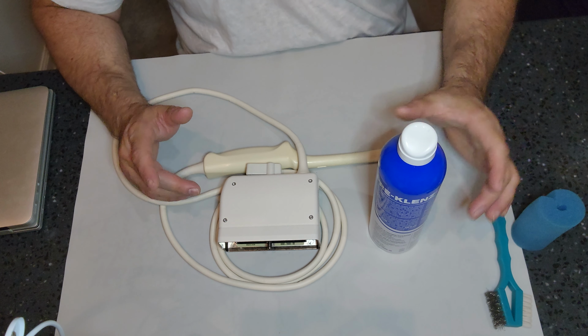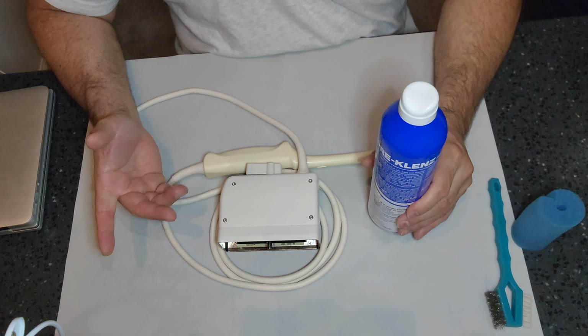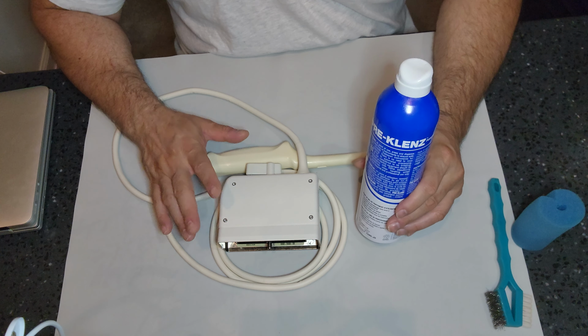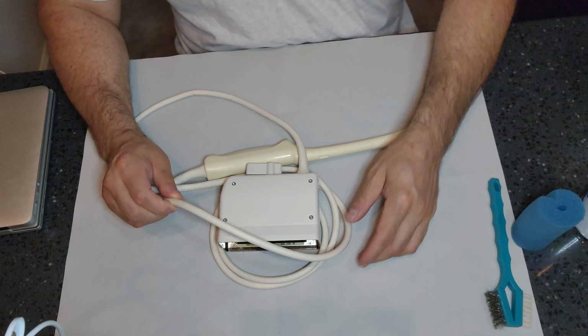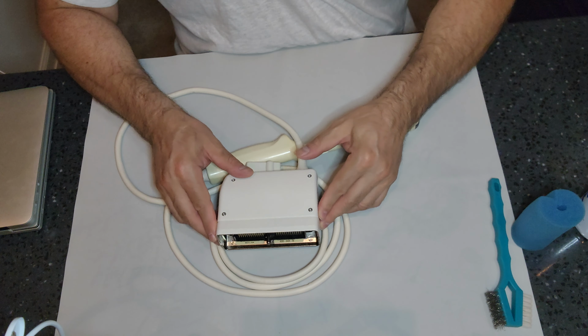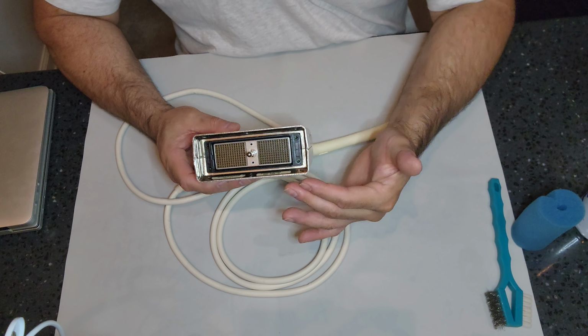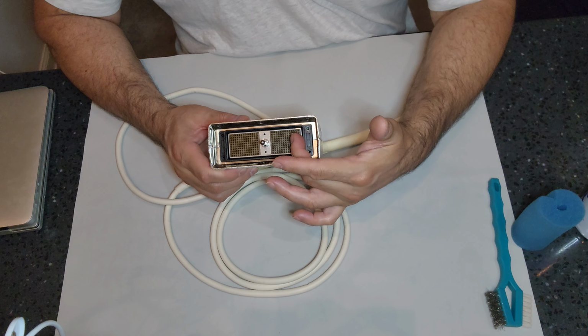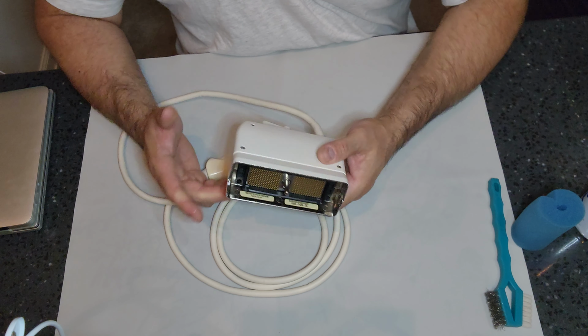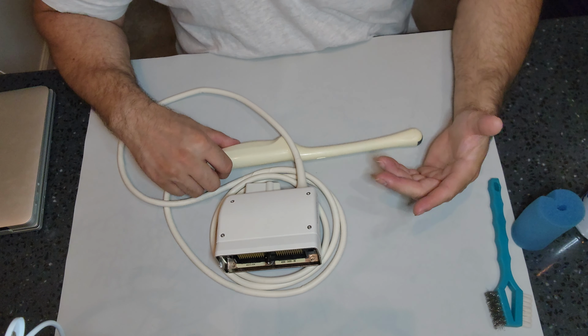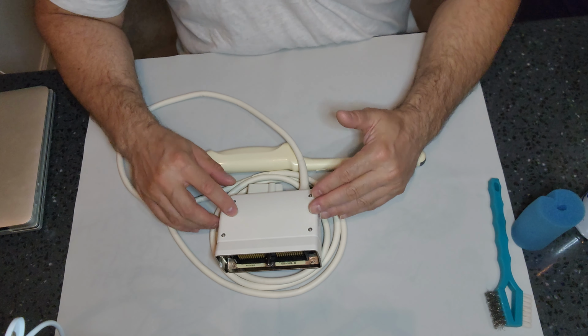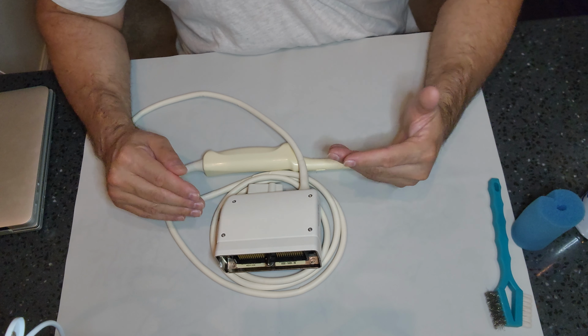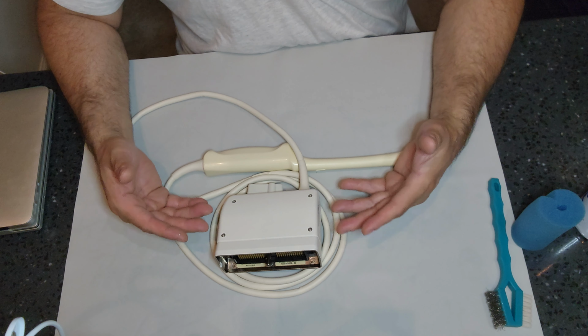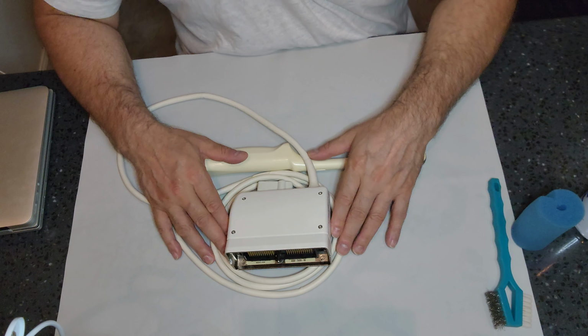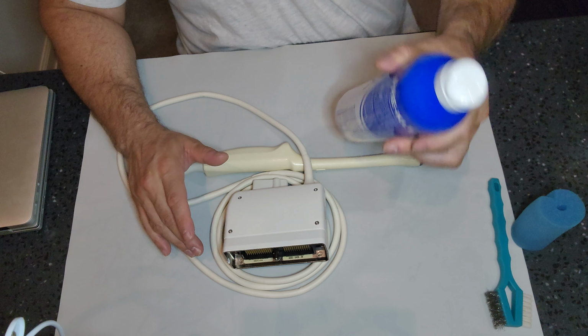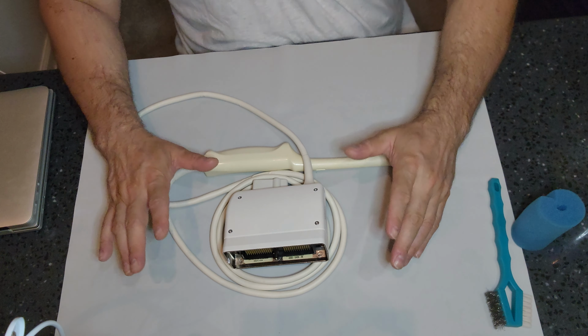Again, we have to look at these IFUs. Can we use an enzymatic spray? Because I've seen places use enzymatic sprays on probes and they wind up damaging the probes. They'll spray the cords and the cords wind up getting tinted from the enzymatic, or they spray the connector box and cause corrosion in there. Because we can't get that enzymatic spray off there, so we wind up having to use some water, and then we cause further damage. So in my opinion, honestly, these probes should have a really good wipe down at point of use prior to getting sent down. A moist towel with sterile water is probably the greatest amount of moisture to use on there rather than an enzymatic spray. But again, refer to those IFUs.